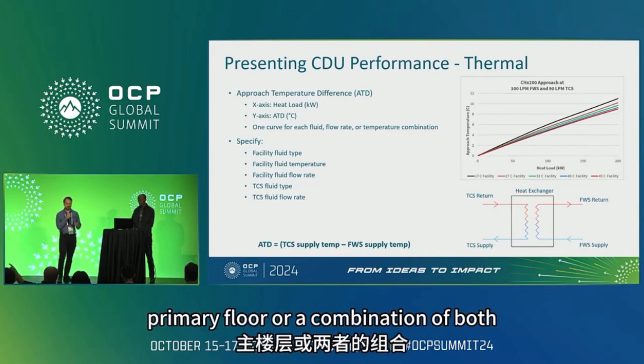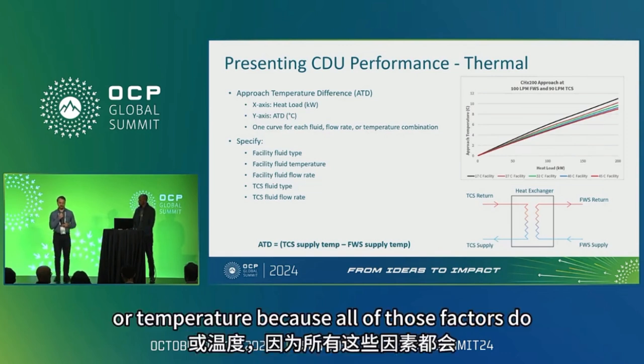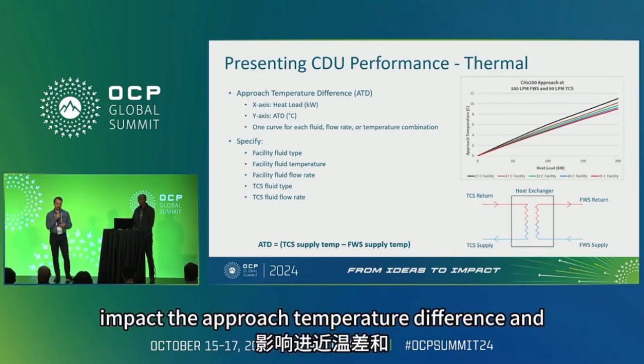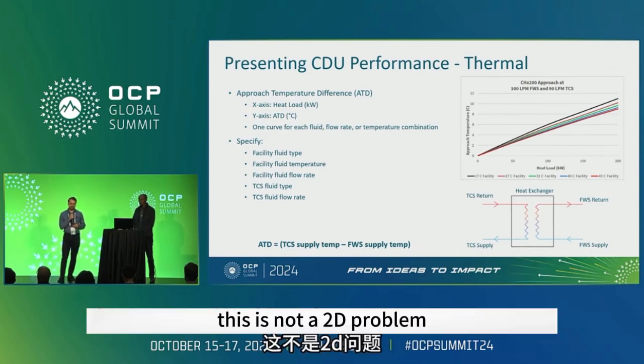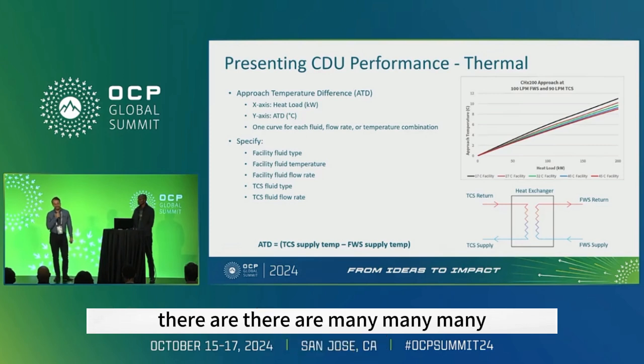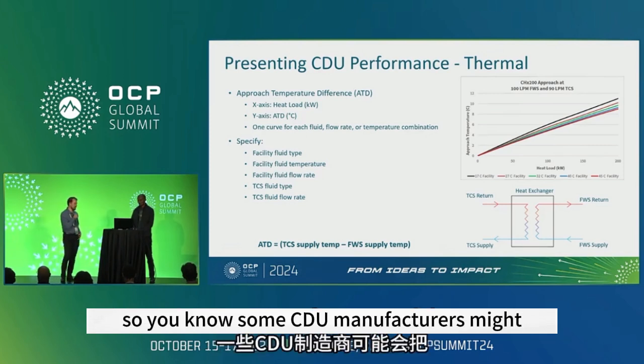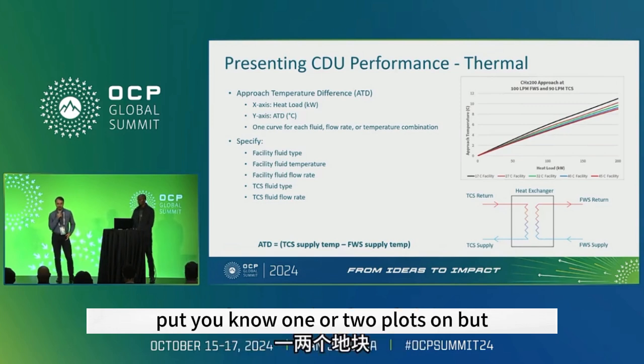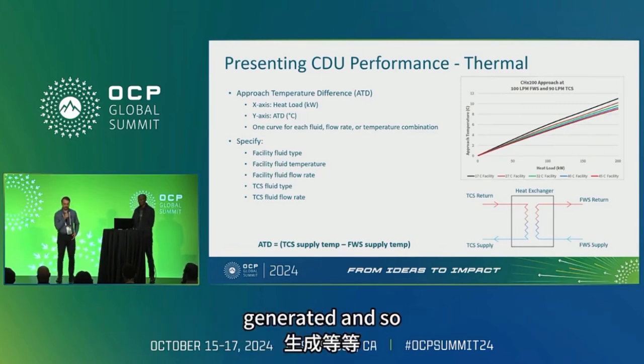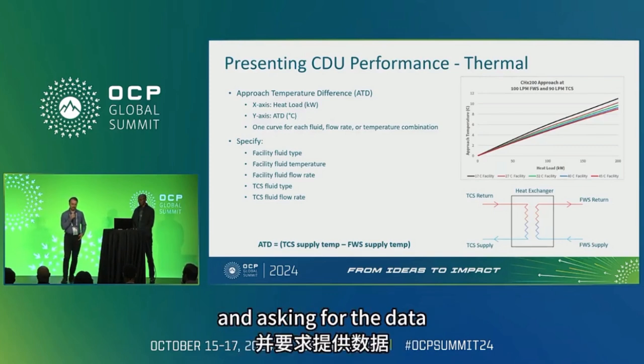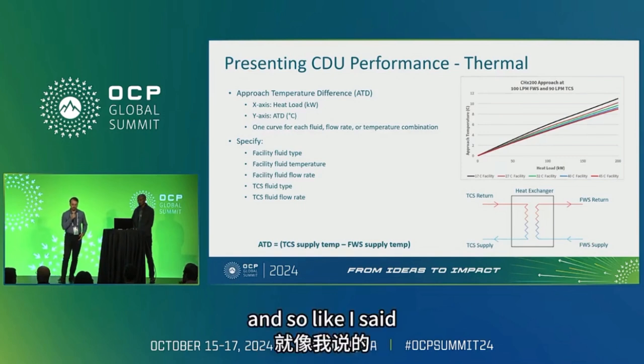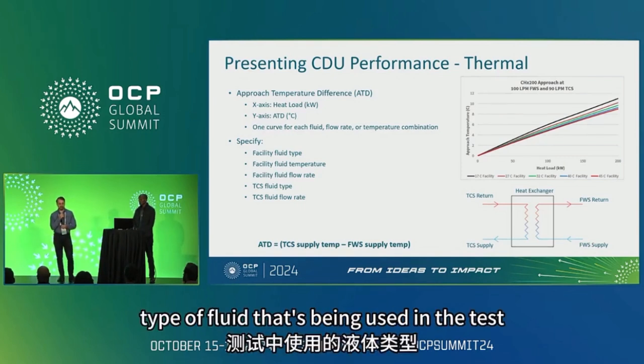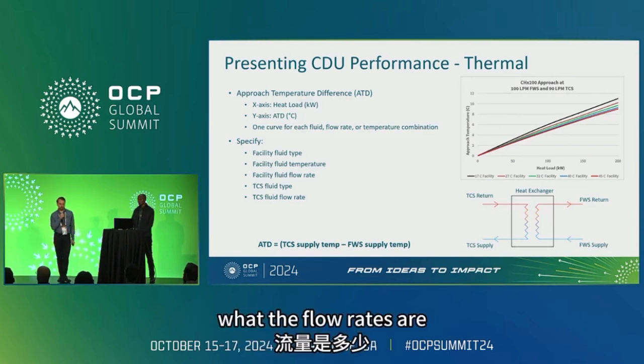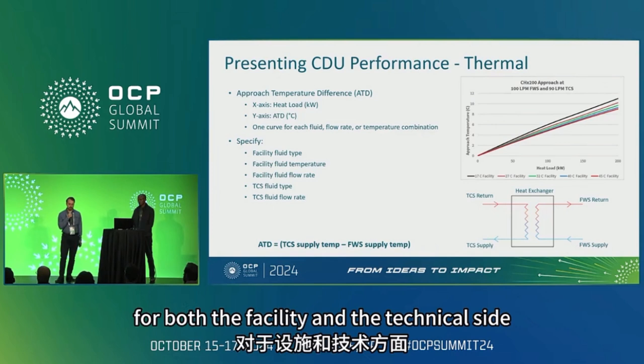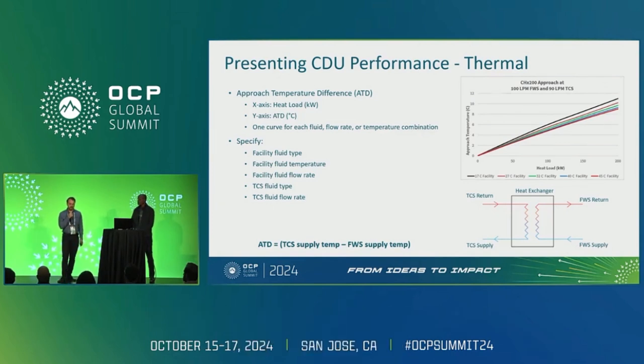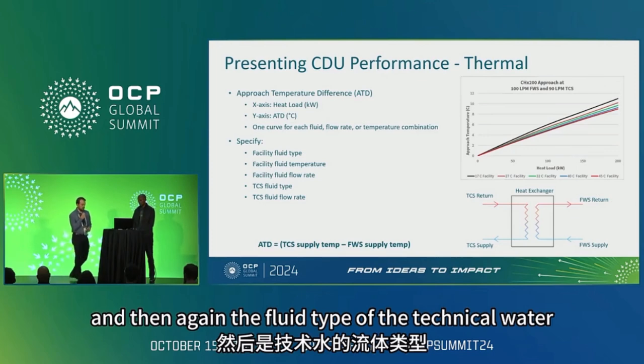a flow rate, that could be a secondary flow rate, a primary flow rate, or a combination of both, or temperature, because all of those factors do impact the approach temperature difference, and this is not a 2D problem. There are many factors that come into play here. So some CDU manufacturers might put one or two plots on, but there's certainly a lot more that could be generated. And so if you're looking into CDUs, make sure you're considering that and asking for the data at the right data points. And so like I said, you have to specify the type of fluid that's being used in the test, what temperature that fluid's at, what the flow rates are for both the facility and the technical side, and then again, the fluid type of the technical water.